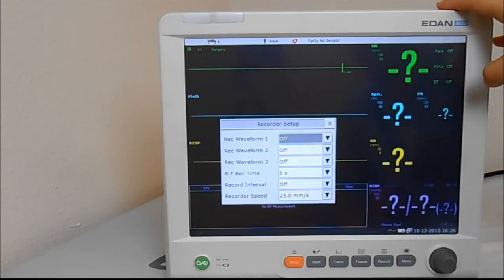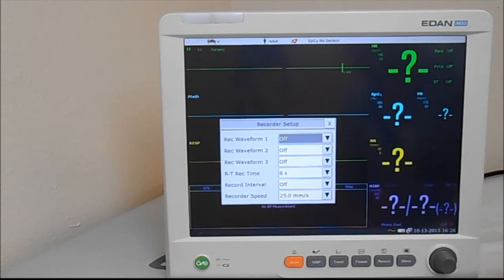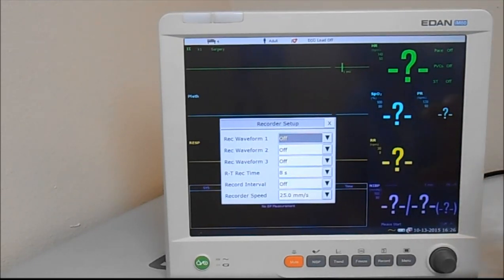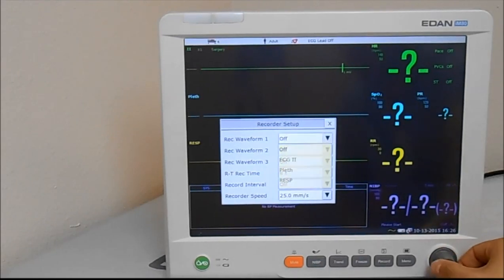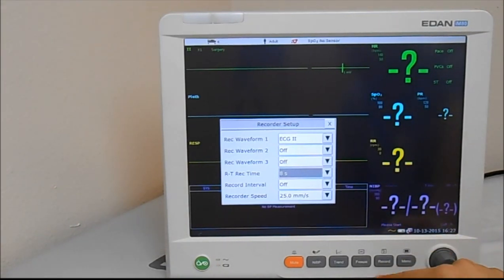can print up to 3 waveforms at a time, but if you want to keep it simple and very easy to read, we'll set it so that the monitor only prints the ECG. So rec waveform 1, we'll set it to ECG 2. Waveform 2, we set it to or leave it at off. Waveform 3 is off.